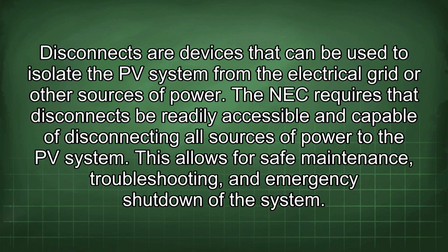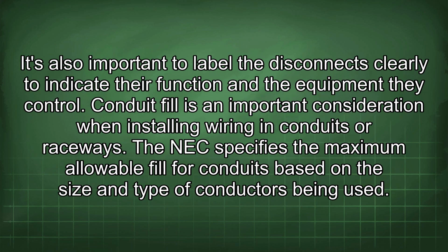Disconnects are devices that can be used to isolate the PV system from the electrical grid or other sources of power. The NEC requires that disconnects be readily accessible and capable of disconnecting all sources of power to the PV system. This allows for safe maintenance, troubleshooting, and emergency shutdown of the system. It's also important to label the disconnects clearly to indicate their function and the equipment they control.